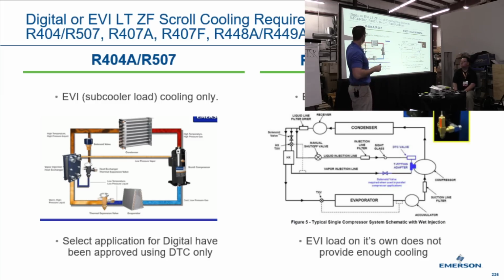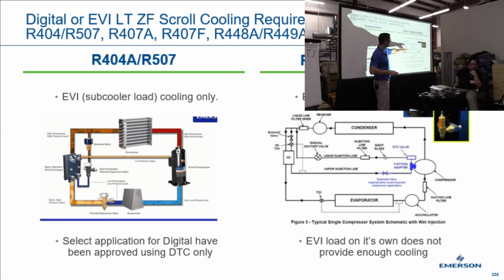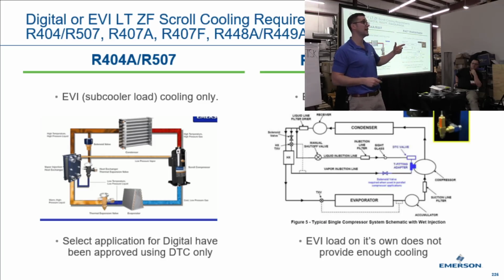But if I have an EVI and I retrofit the gas from 404 to a newer refrigerant that runs hotter, I got to use the DTC valve as well as the EVI. So there will be a T involved in there. Okay, so this is something you need to look at, because when we're changing refrigerant, now there's different dynamics in that system.